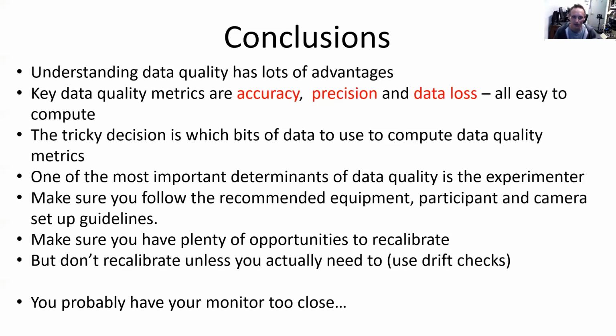And give yourself opportunities to recalibrate. I skipped over this point, but don't recalibrate unless you need to. People always ask me how often should we recalibrate, and the answer is you should only ever recalibrate if you need to, but you should give yourself lots of opportunities to check whether you need to, and then if you do need to, then do it. And again, you probably have your monitor too close.